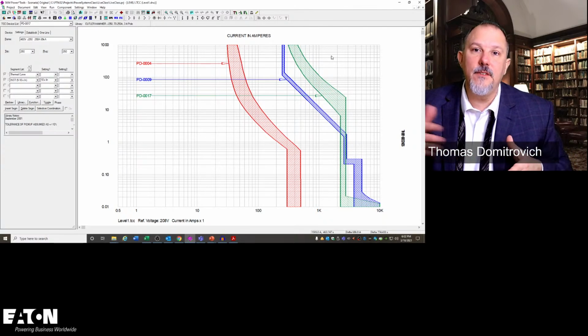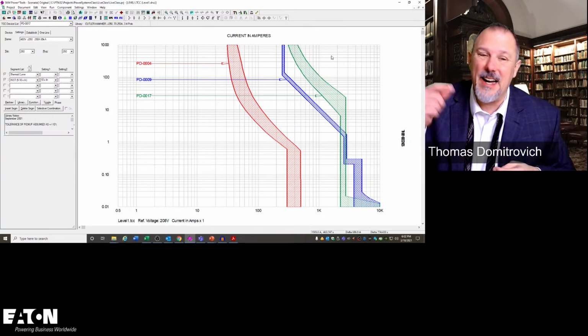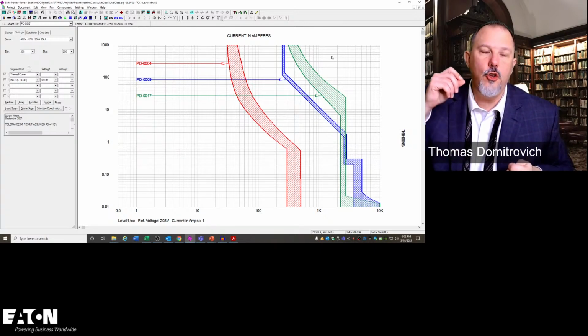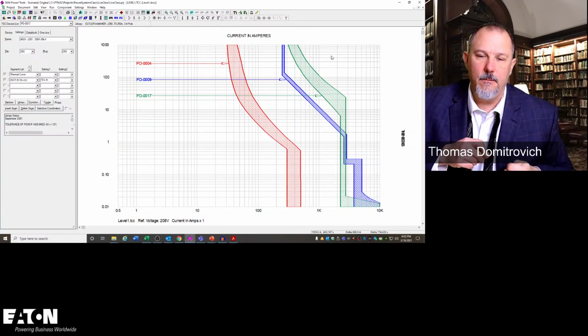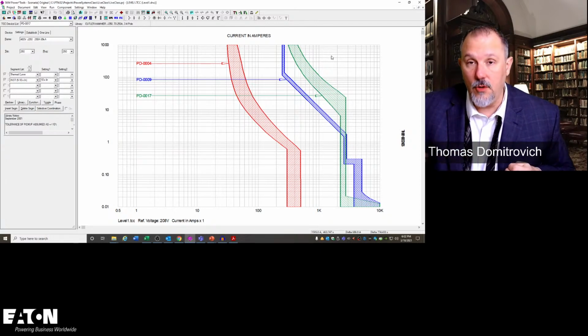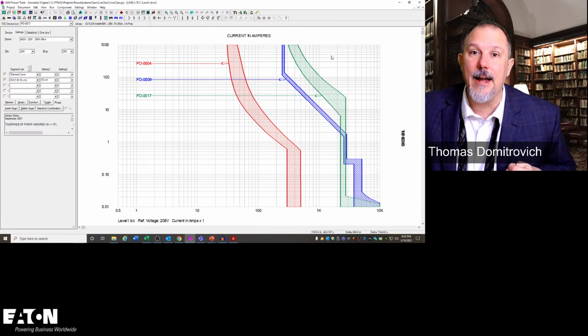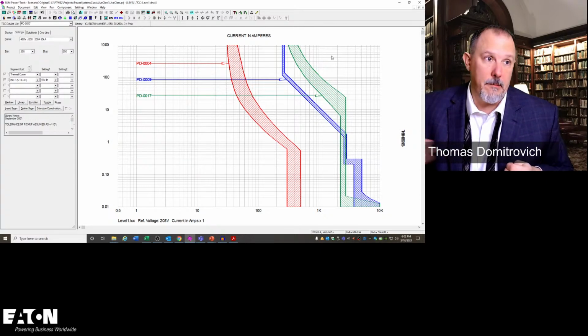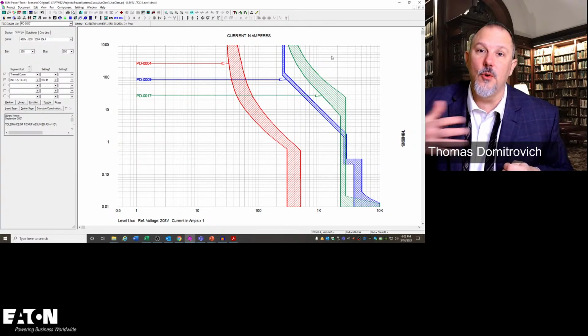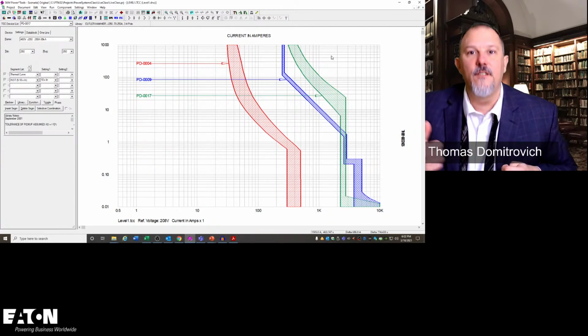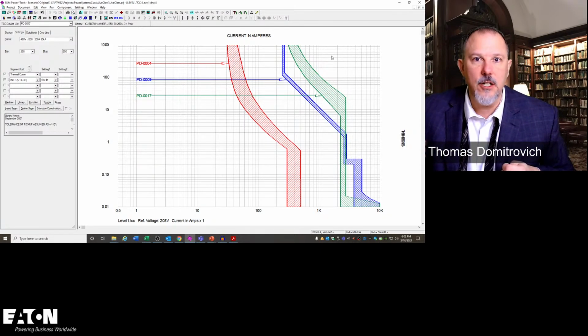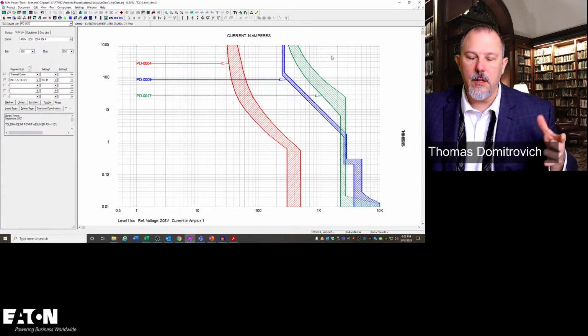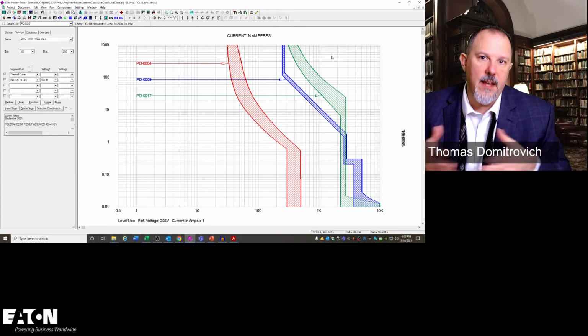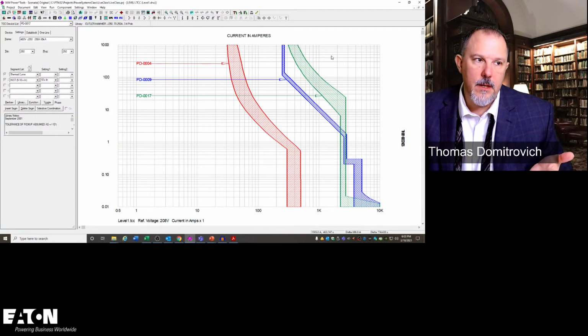And it's a level of assurance, but if you want to be 100% positive that under all fault conditions you will never have a cascading event because of miscoordination, then you've got to go to the three-phase bolted fault current, because you know you're not going to get anything higher, since that's the maximum available fault current. And it's probably a theoretical number that's higher than what you'll ever get because I'm ignoring some impedances. If you go back to that impedance diagram from my earlier classes, I didn't include the bus impedances. I didn't include overcurrent device impedances. I would rearrange things to show all my motors on to give me the maximum available fault current that I could possibly see.